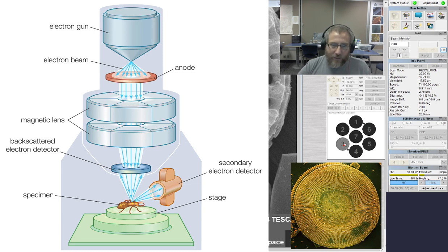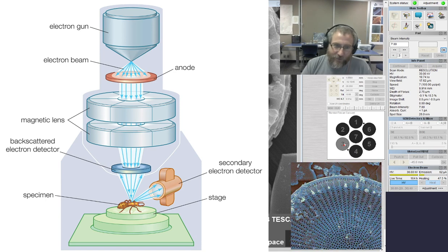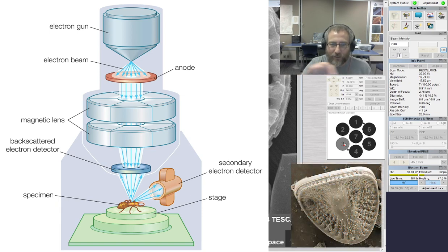And inside of that secondary electron detector is like a photoreceptor sort of thing that when electrons hit it, they light up. And when more electrons hit it, it lights up more. And when fewer electrons hit it, it's dimmer. So it goes point by point, each place that the electron beam is sampling in the image that you're seeing in a line. So the scan that we're seeing is actually building the image point by point.